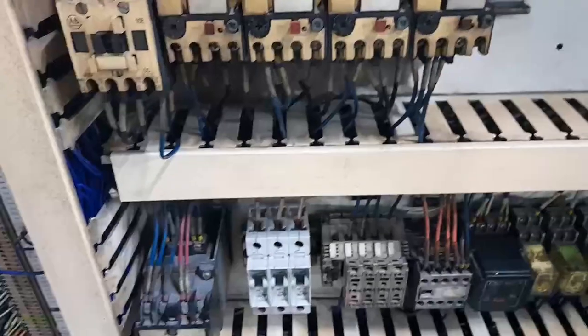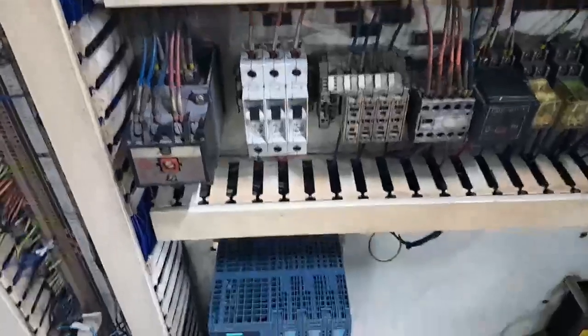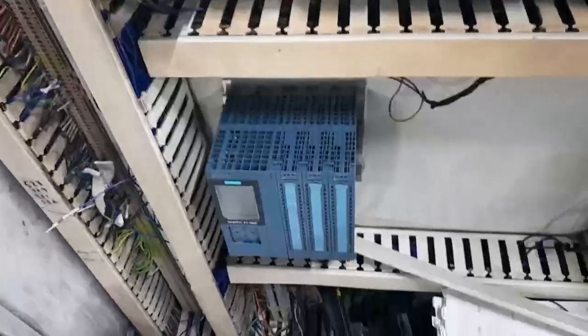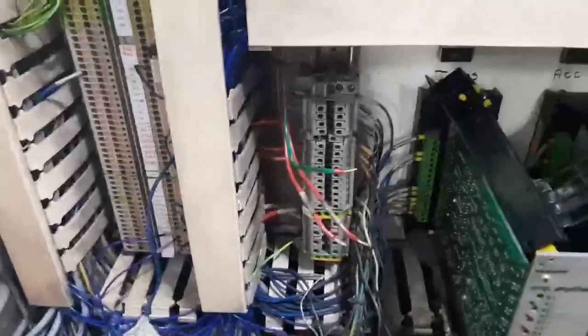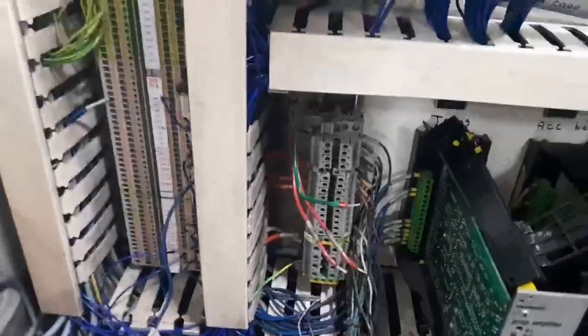And when it comes to an arc flash or blast, the risk is that the flash can cause severe burns, can cause blindness or death due to the intense heat, which basically goes to about 40,000 degrees Celsius within a split second. So that is high temperature. Causes of arc flash could be short circuits, equipment failure, or equipment contact with live parts during commissioning. So when you're working on an electrical panel, just make sure that you are working safely.